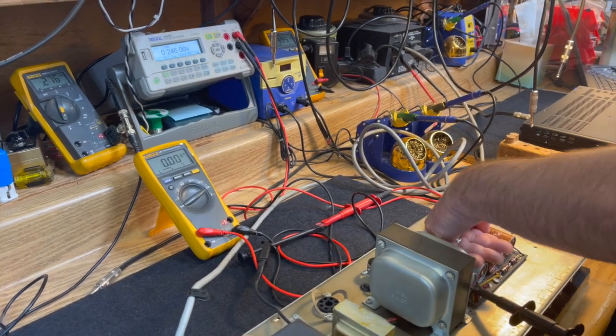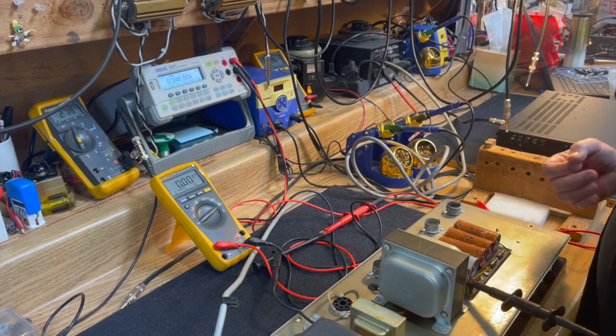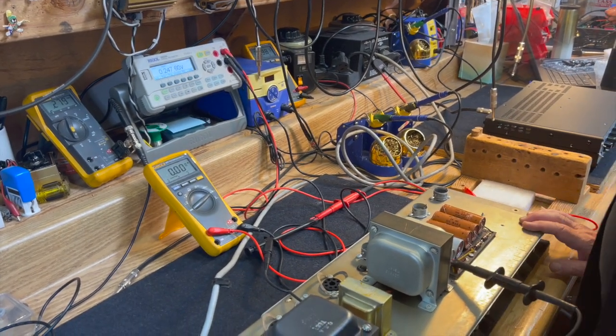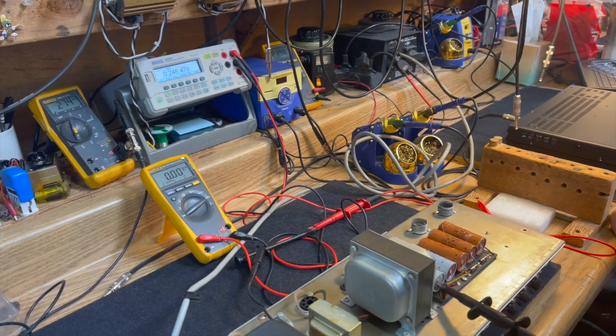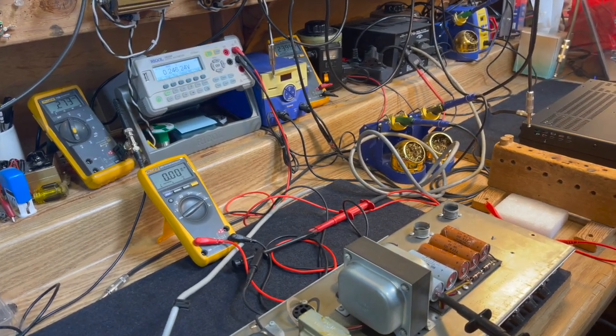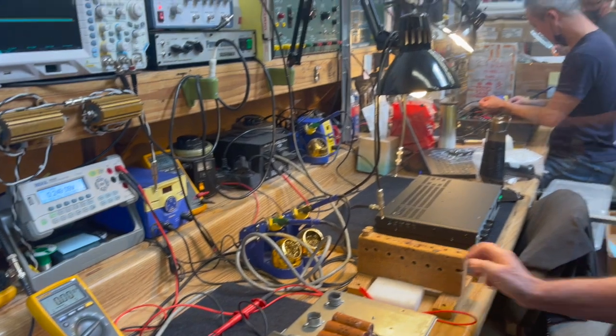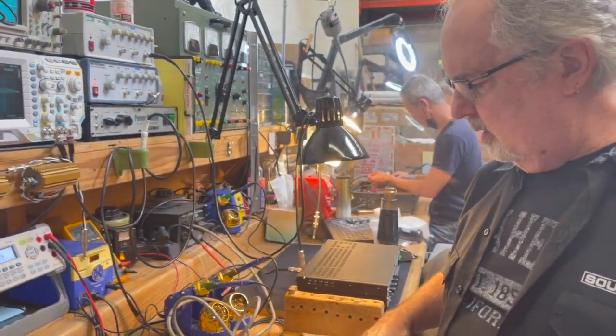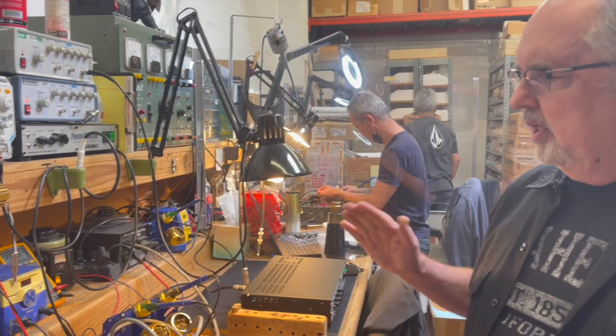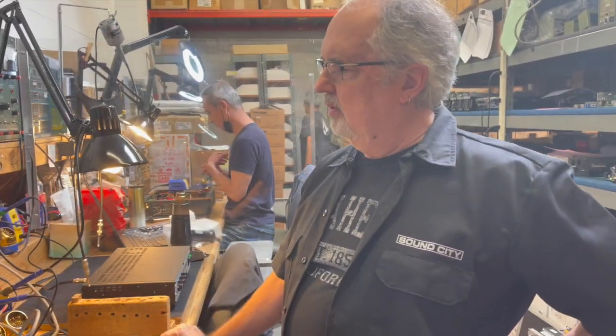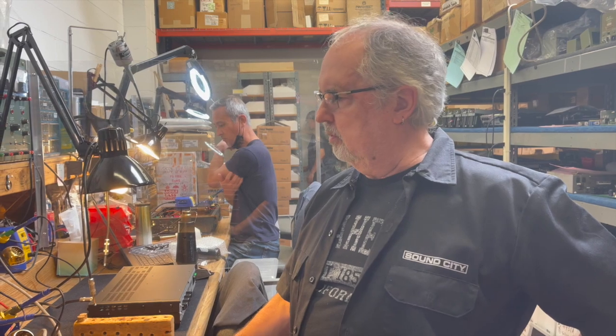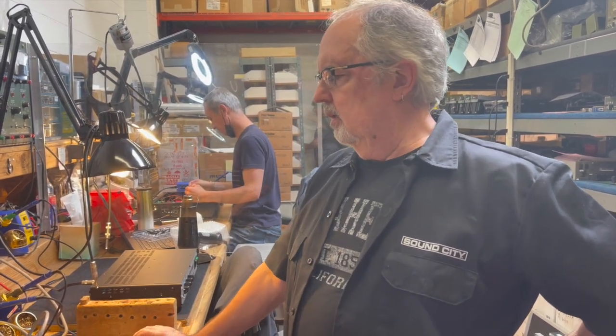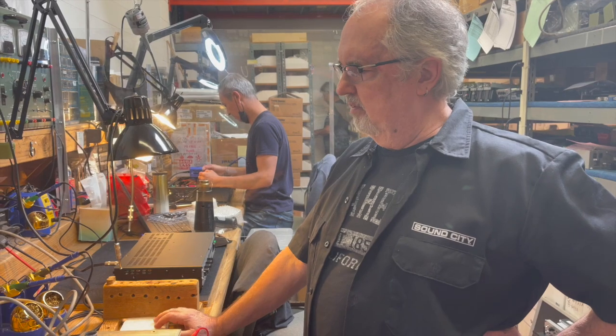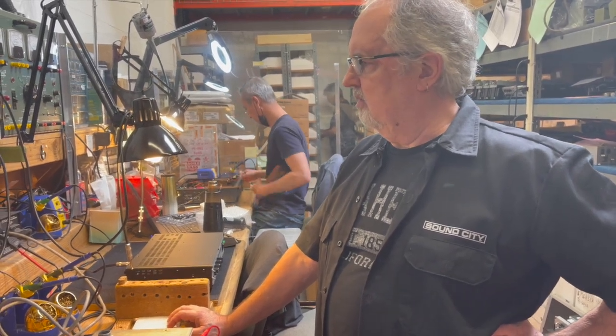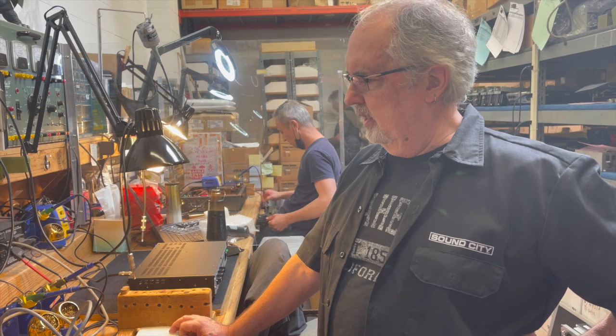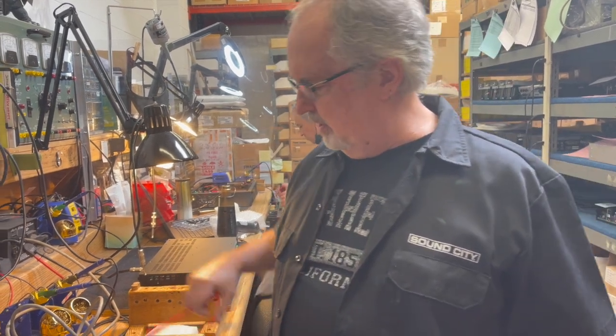We're a bunch of happy little campers right at the moment. And so we're at this voltage, and I don't think sitting here for another 10 or 20 minutes is going to make any difference, because we didn't see a rise that's starting to level off like I described earlier. We just saw a gradual residual increase in the combined residual leakage current of the capacitors themselves. So that's not anything to be concerned about, to the point where I'm ready to do this.